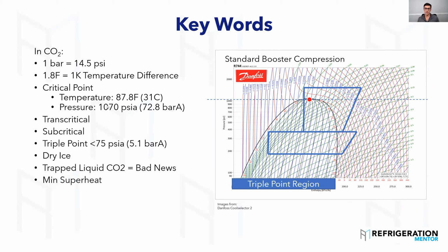No? Okay. So, minimum superheats. Now, this is something that's super important. When I was working at Copeland, I used to do a lot of field support and take a lot of calls. And I got a call after there were, I believe, 14 compressor replacements. They just kept sending them compressors. This was back in 2015, I think. 14 compressor replacements on a rack because of superheat.